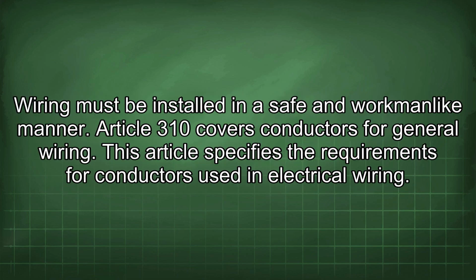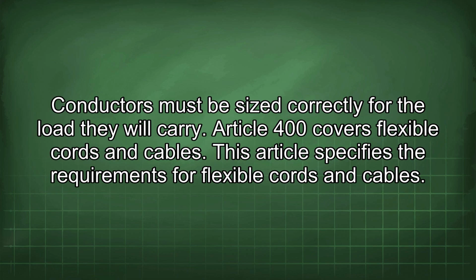Wiring must be installed in a safe and workmanlike manner. Article 310 covers conductors for general wiring. This article specifies the requirements for conductors used in electrical wiring. Conductors must be sized correctly for the load they will carry.